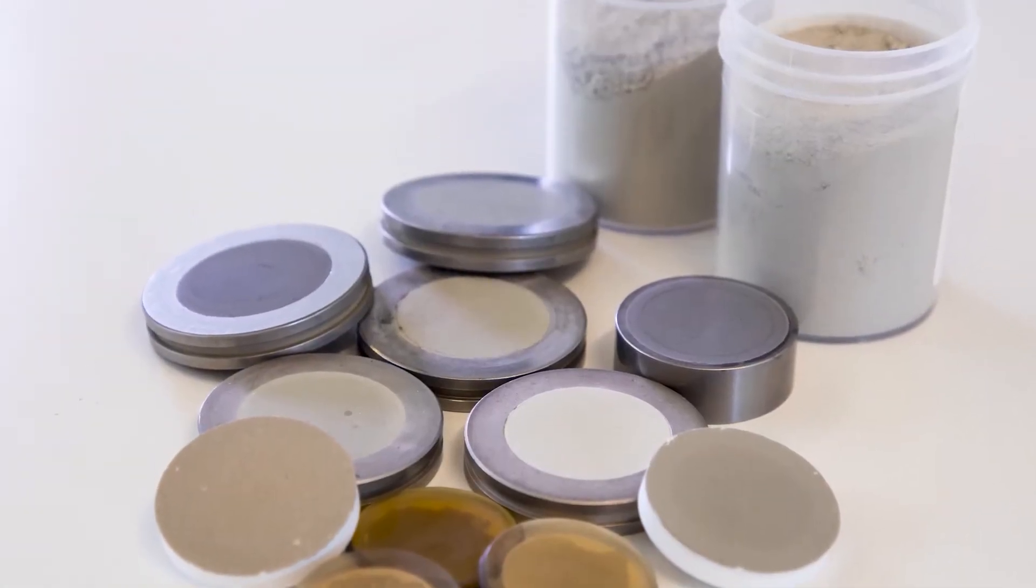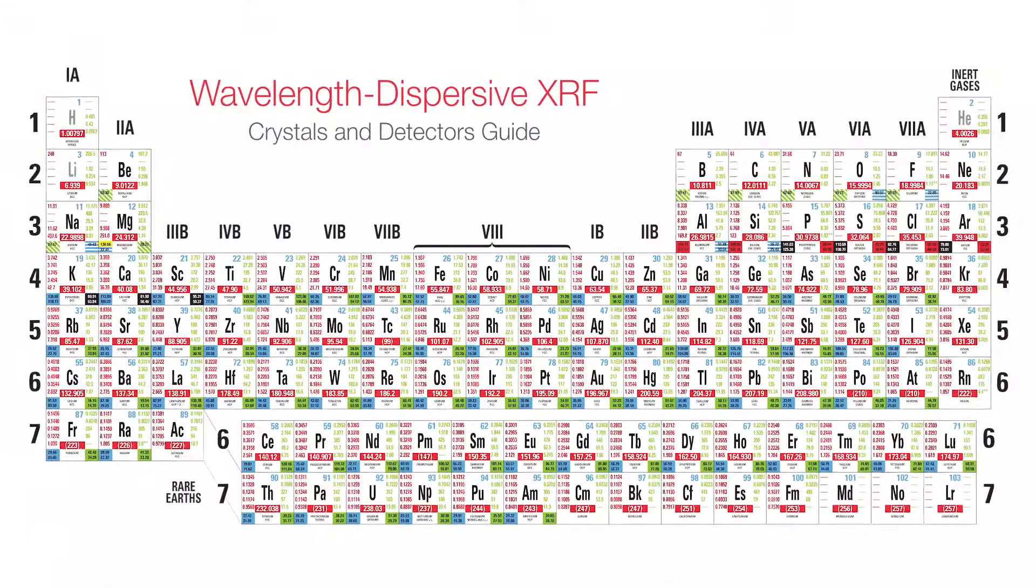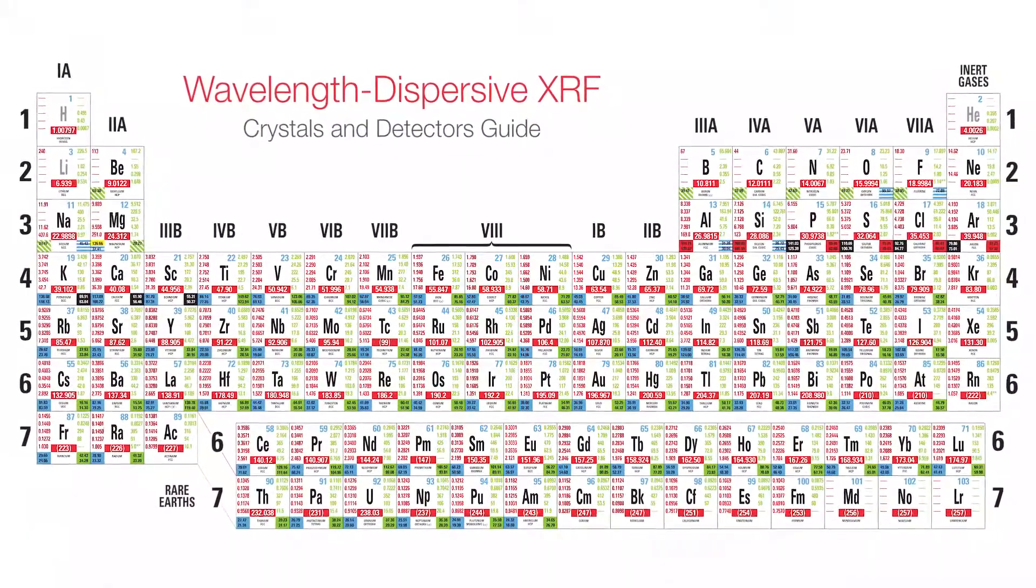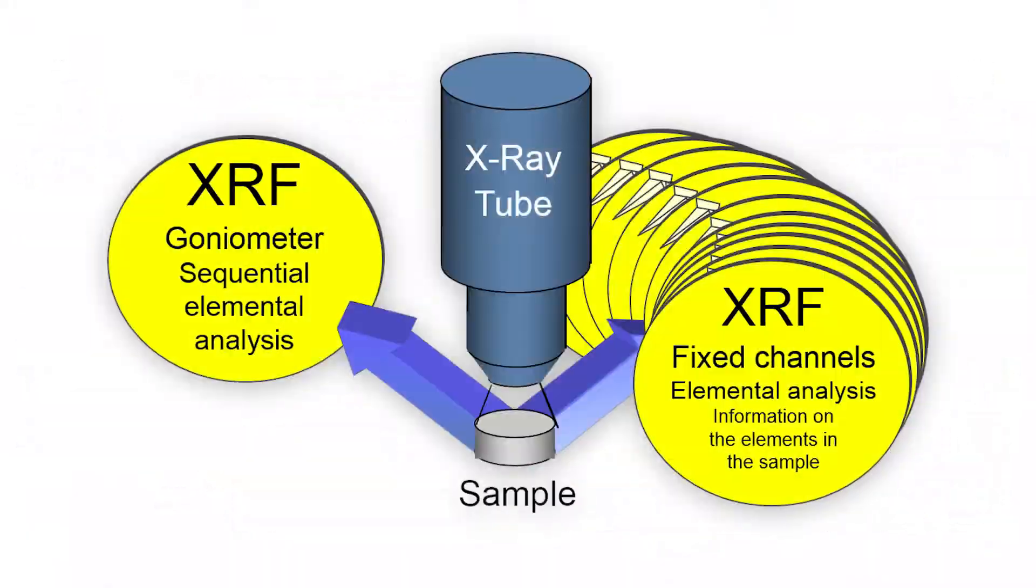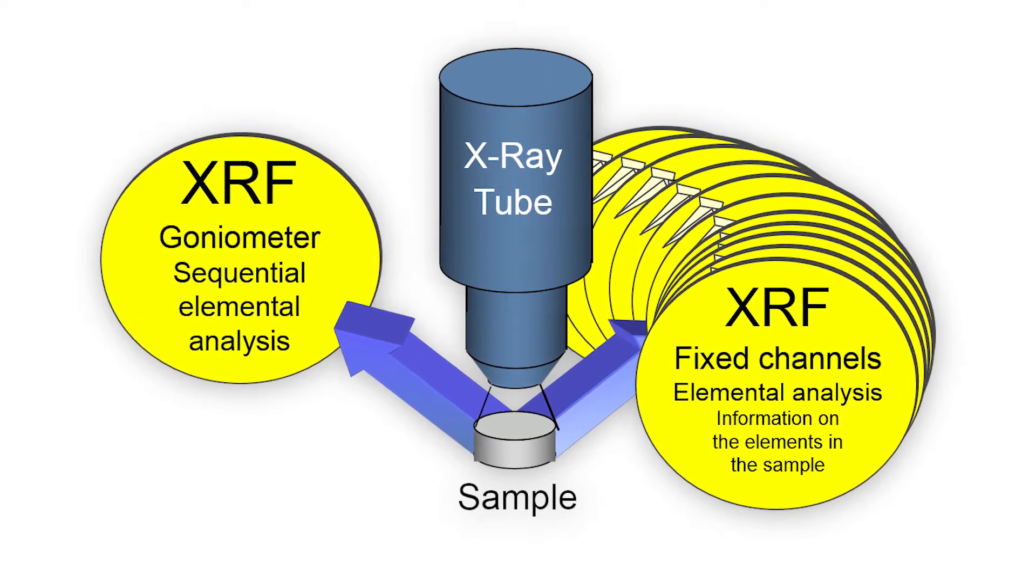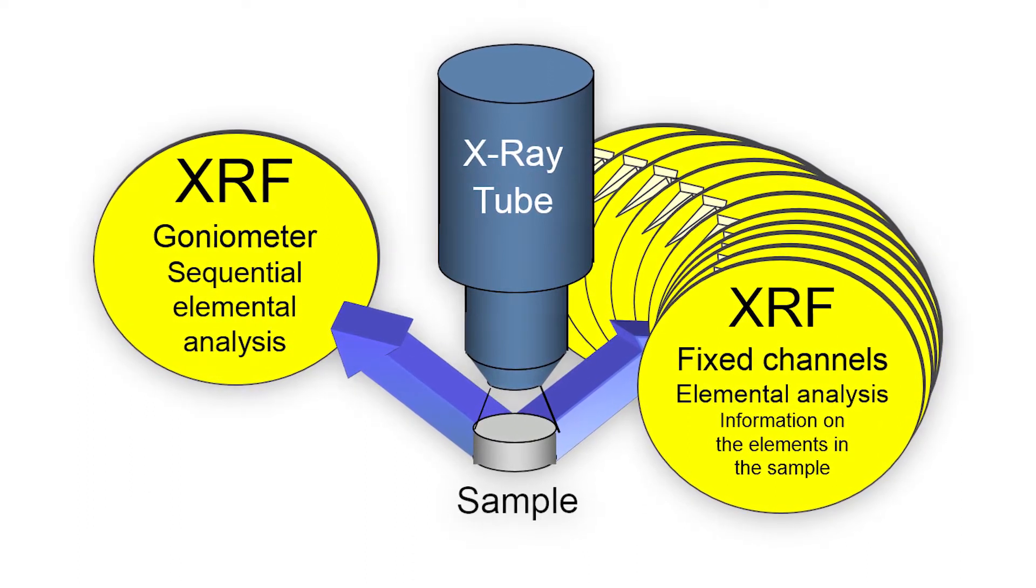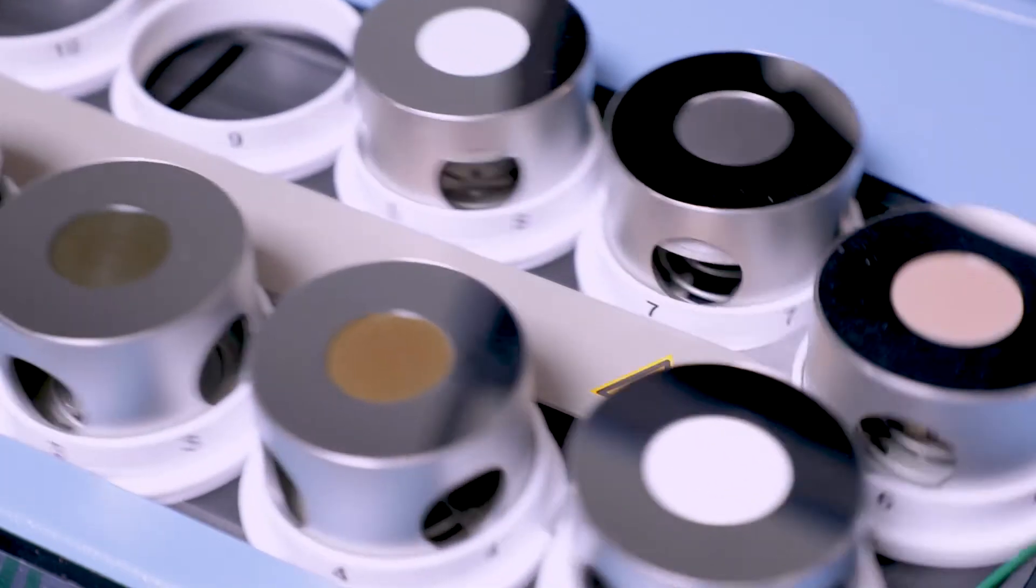Up to 90 elements can be detected in concentrations ranging from parts per million to 100%. A series of fixed monochromator channels can be fitted alongside the goniometer, which makes the ARL 9900 highly productive. A new sample can be analyzed every minute for up to 30 elements.